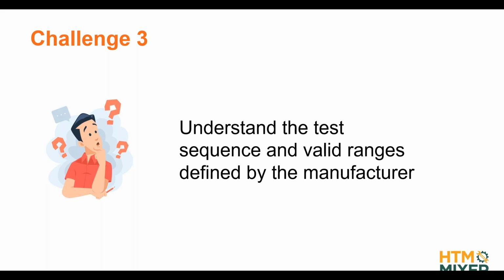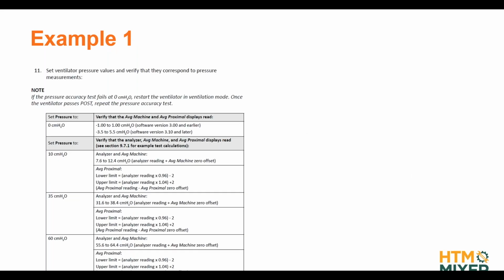The last challenge we see often is that the test sequences and valid ranges defined by the manufacturers are sometimes quite challenging to understand. So here's an example, and don't worry if you can't read all of that. This is an example of a ventilator where we need to calibrate different pressure levels. First at 0 pressure, then at 10, 35, and 60 centimeters of water. And this is very typical, right? You have to set up different pressures on your ventilator, and then you have to measure with your analyzer whether or not these pressures are within a specific range. So it sounds really easy. Here, in this case, you see we need to do something at 0.